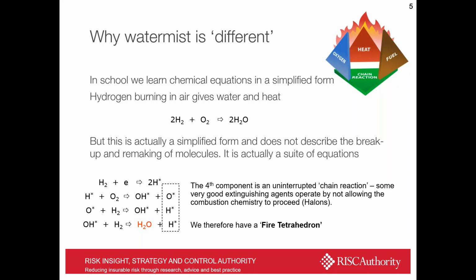Whilst we might be used to our O-level chemistry telling us that hydrogen and oxygen mix to make water in a simple equation, in actual fact, it takes place as a series of steps where bonds are broken and remade between the various compounds that are involved. And while they are in this heightened state of being split up, they form free radicals. And in suppression terms, there is an opportunity for other molecules to be introduced to steal these, so the chemistry of combustion can't complete. And this is probably the most familiar action of some of the gases which have historically been used for fighting fire. So we can really address fire by limiting oxygen, heat or fuel, or interrupting the chemistry of combustion itself.